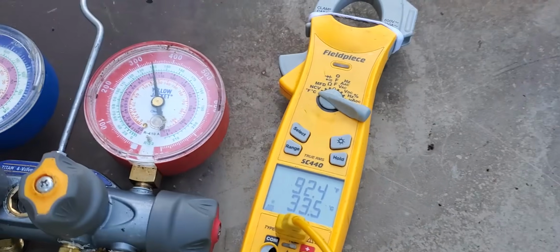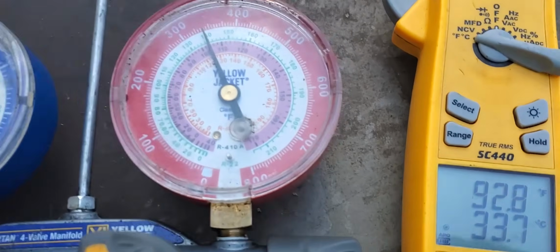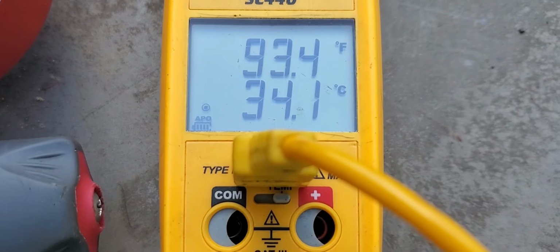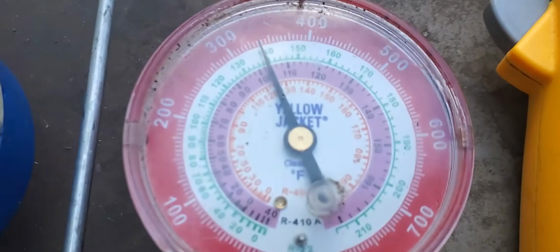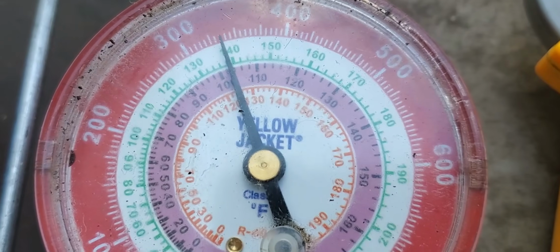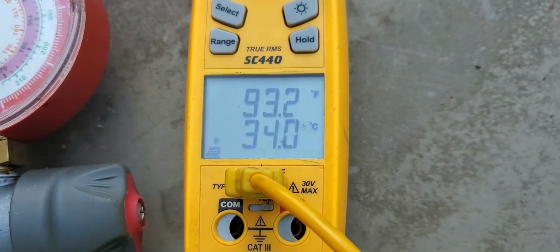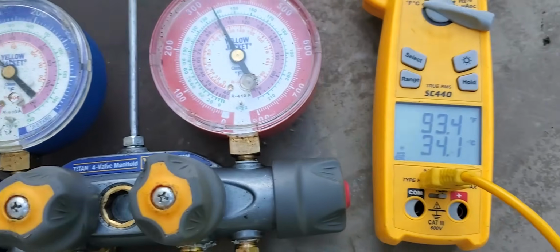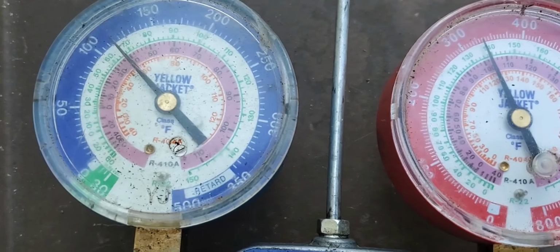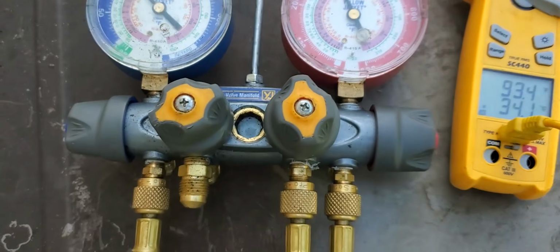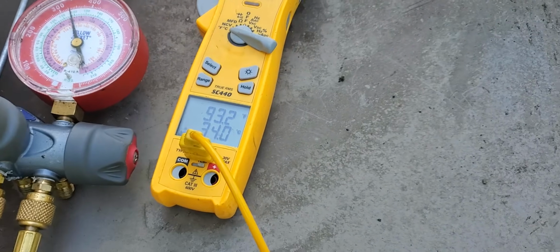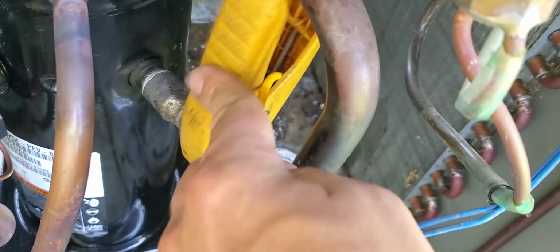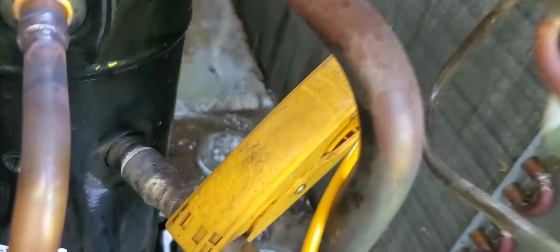Record any difference. If the superheat is low, the problem could be a malfunctioning metering device, inadequate airflow through the evaporator, or an excessive refrigerant charge. If the superheat reading is too high, the problem could be a restriction in the liquid line, a malfunctioning metering device, moisture in the system, an excessive heat load, or an insufficient refrigerant charge. Once the target superheat is found, it is compared to the actual superheat, which is determined by the evaporator pressure and the suction line temperature.